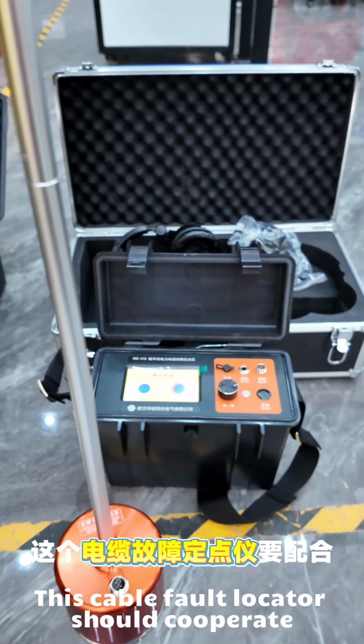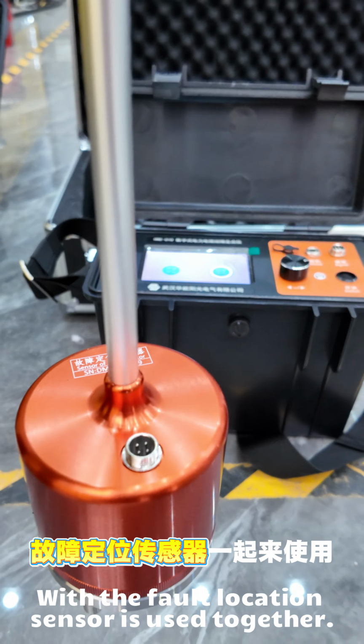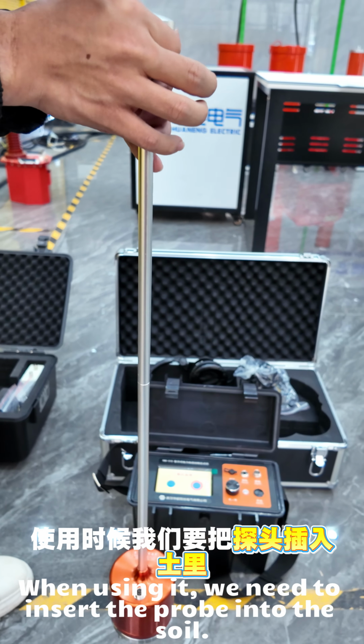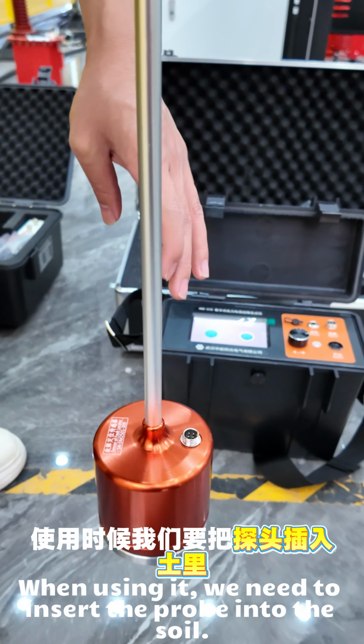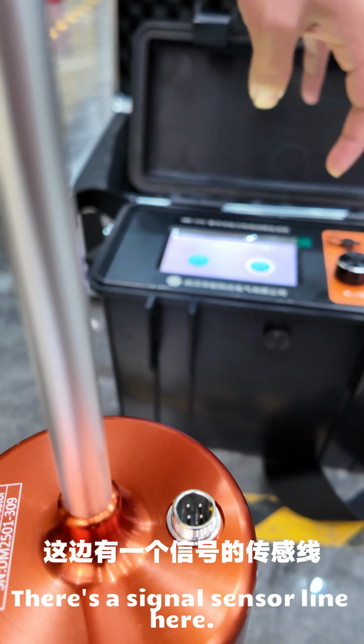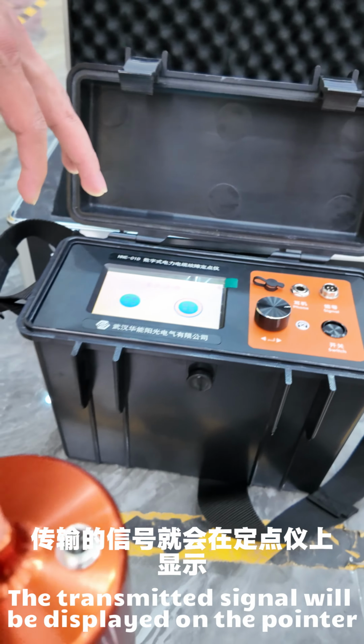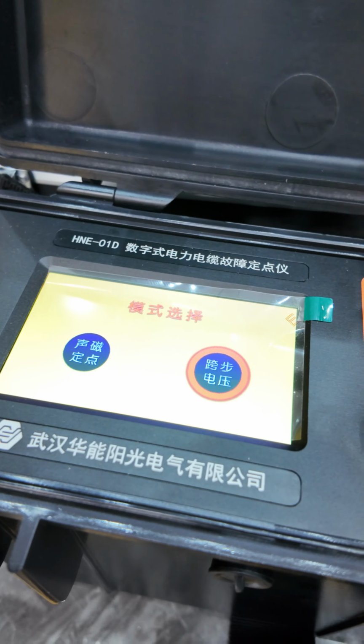Look, just like this. This cable fault locator should be used together with the fault location sensor. When using it, we need to insert the probe into the soil. There's a signal sensor line here, connect to this host. The transmitted signal will be displayed on the pointer.